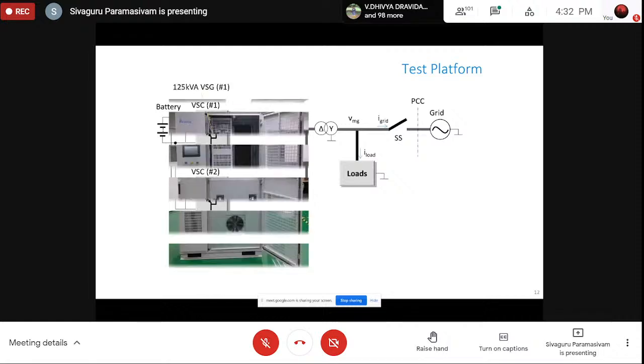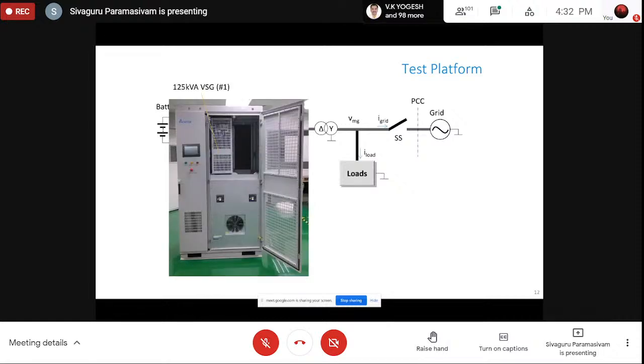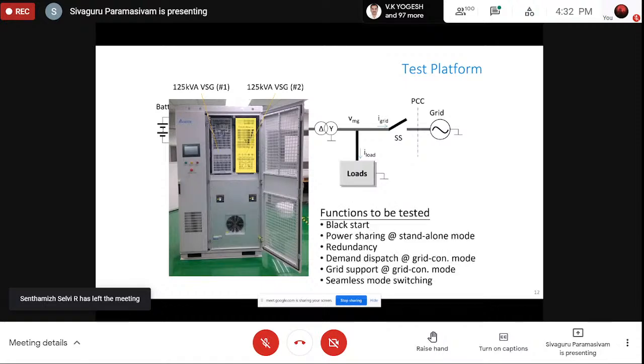Well, we have also tested this kind of system. This shows some of the actual images showing how we parallel up. That's what we call black start. Black start is when we have a complete blackout on the grid side, but still with the renewable assets, we want to energize the grid. It is called black start. We can also do power sharing. When we have higher loads, we can couple multiple of these units in parallel.